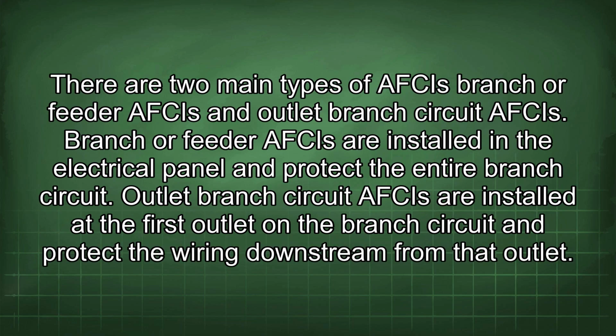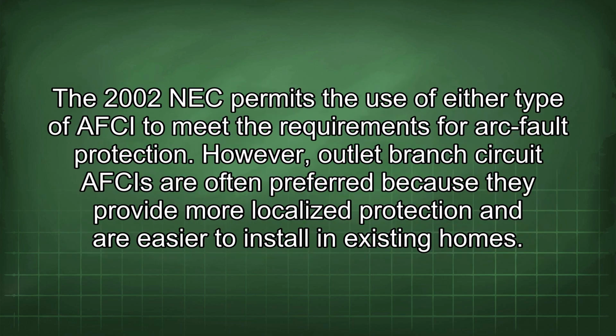There are two main types of AFCIs: branch or feeder AFCIs and outlet branch circuit AFCIs. Branch or feeder AFCIs are installed in the electrical panel and protect the entire branch circuit. Outlet branch circuit AFCIs are installed at the first outlet on the branch circuit and protect the wiring downstream from that outlet. The 2002 NEC permits the use of either type of AFCI to meet the requirements for arc fault protection.